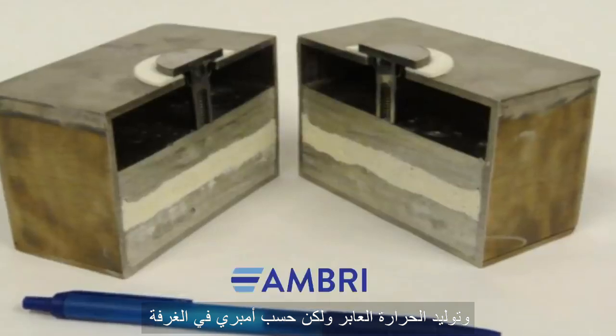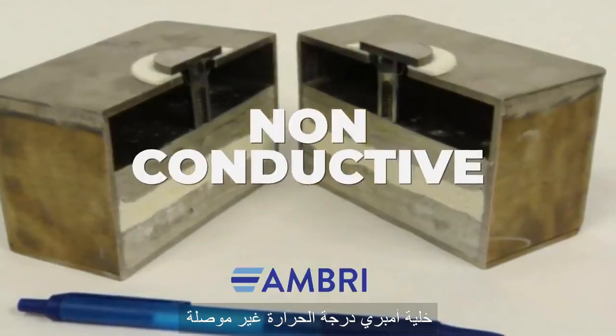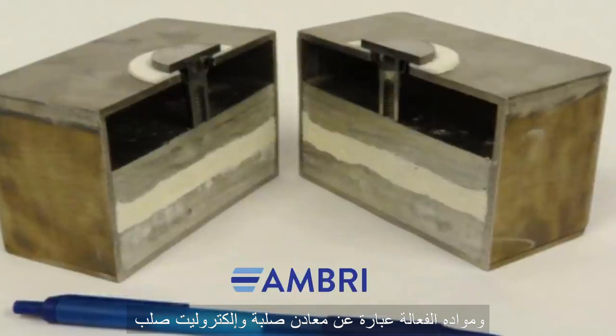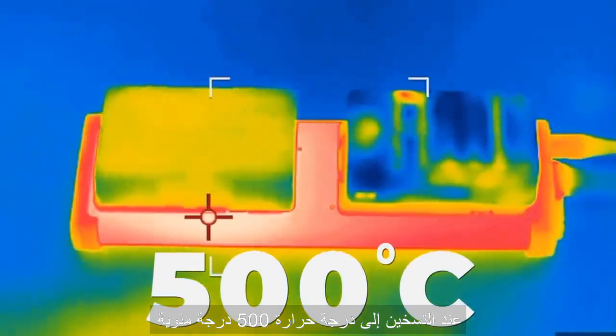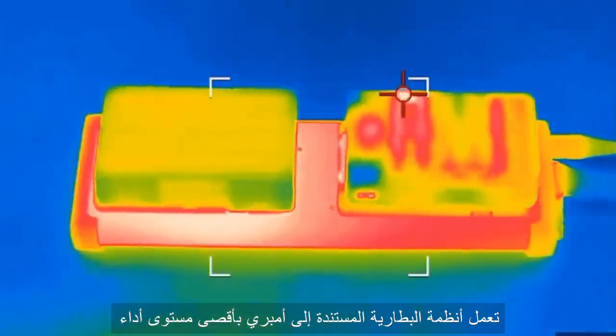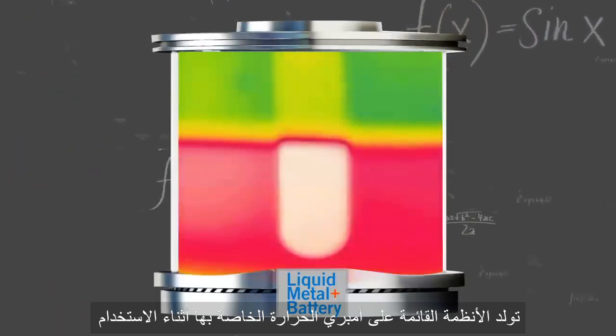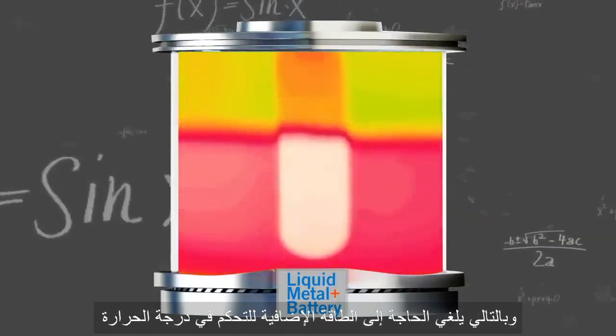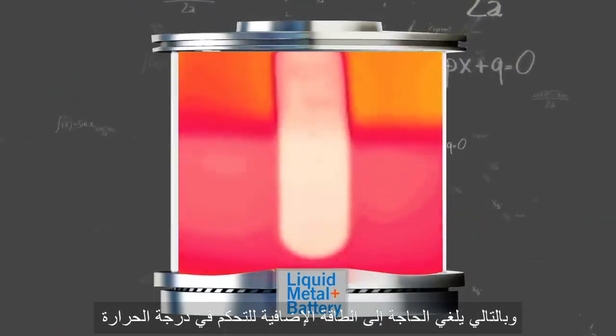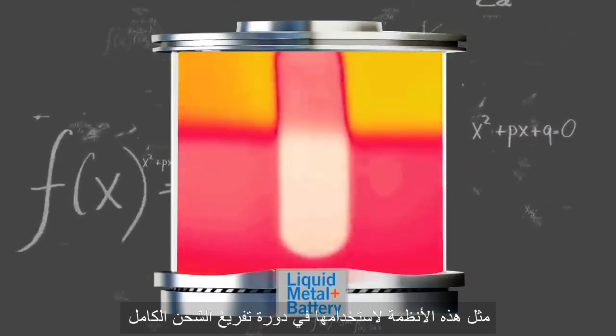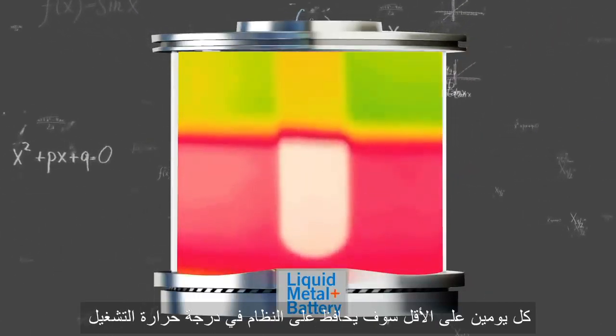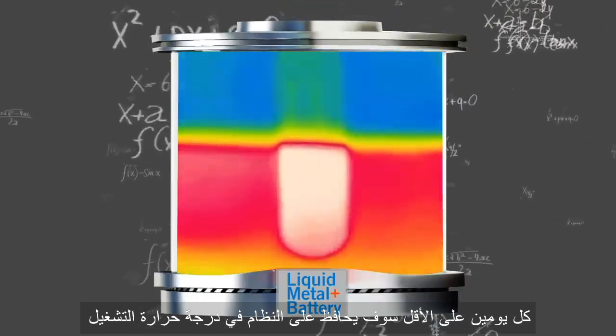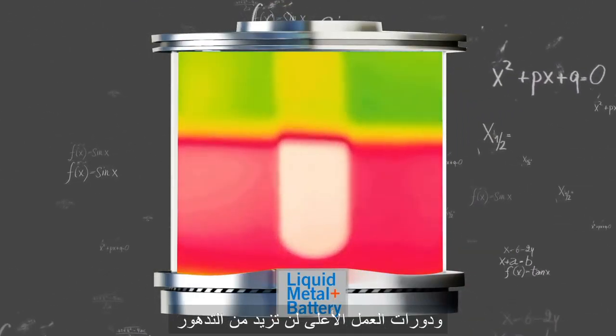However, according to Ambri, at room temperature, Ambri's cell is non-conductive and its active materials are solid metals and a solid electrolyte. Upon heating to 500 degrees Celsius, Ambri-based battery systems operate at maximum performance level, no matter the external temperature, and require no power-hungry air conditioning. Ambri-based systems generate their own heat during use, thereby eliminating the need for auxiliary power for temperature control. These systems like to be used. A full charge-discharge cycle at least every 2 days will keep the system at its operating temperature, and higher duty cycles will not increase degradation.